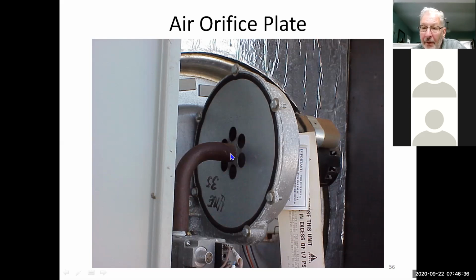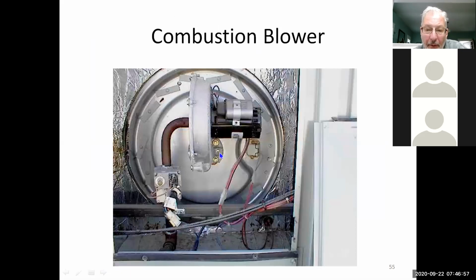I've seen spiders in there and bugs, you know, bees, all kinds of things. The gas pressure won't change, but the volume does change. So make sure that this manifold is open. Make sure we're running the proper gas pressure. Make sure that the inducer is clean. Make sure that the back of the heat exchanger where the inducer sits, this little plate right here, there's a screen inside here. If that gets dirty, it's not going to work right. So there's a lot of things to look for if it's not burning properly.